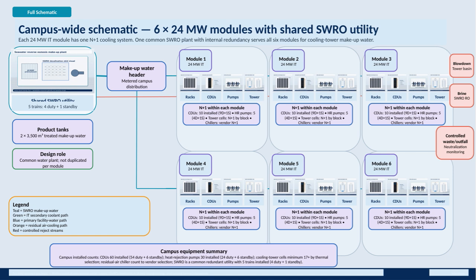The entire campus shares a common SWRO utility, which includes 5 trains for operational duty, and 1 is on standby for redundancy. This shared SWRO plant provides treated makeup water, stored in 2 large product tanks, each holding 3,500 cubic meters. This centralized design avoids duplicating water plants in each module. Makeup water is distributed via a metered header system across the campus, ensuring precise control and monitoring.